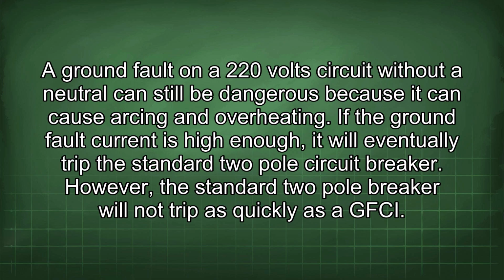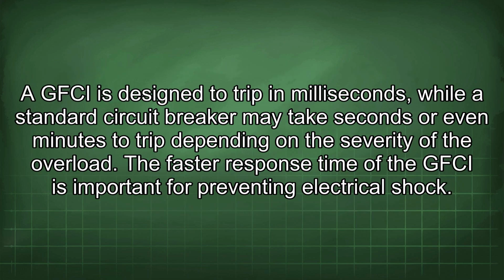A ground fault on a 220-volt circuit without a neutral can still be dangerous because it can cause arcing and overheating. If the ground fault current is high enough, it will eventually trip the standard two-pole circuit breaker. However, the standard two-pole breaker will not trip as quickly as a GFCI. A GFCI is designed to trip in milliseconds, while a standard circuit breaker may take seconds or even minutes to trip depending on the severity of the overload. The faster response time of the GFCI is important for preventing electrical shock.